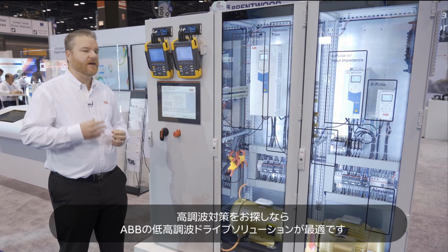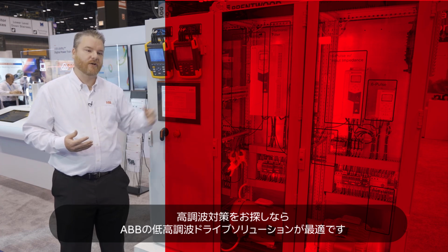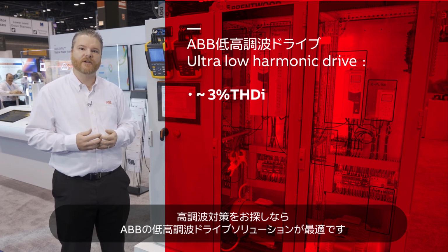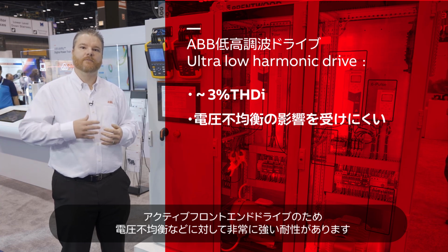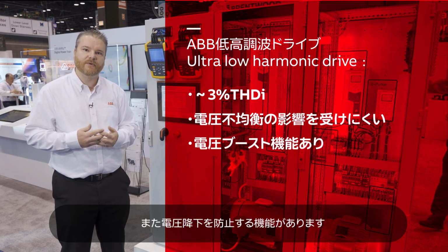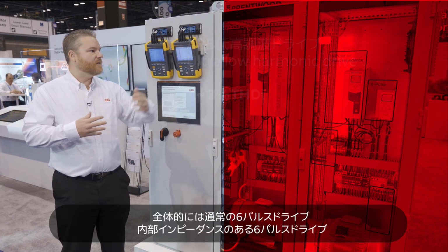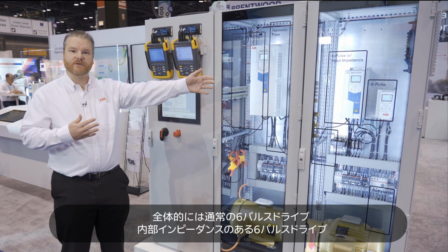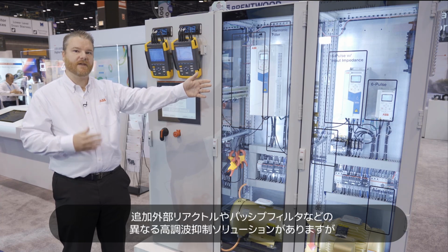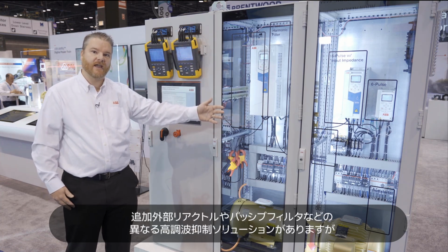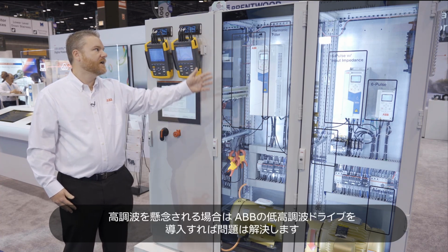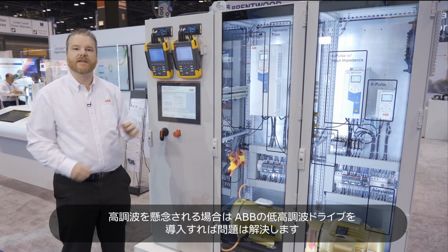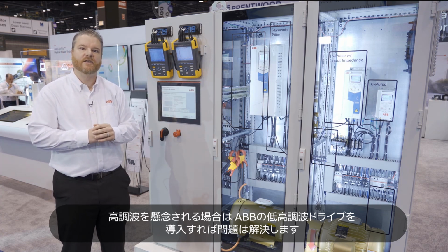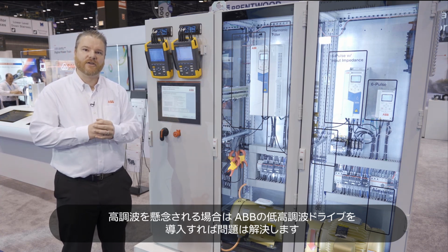So if you're looking for the ultimate in harmonic mitigation, the ultra-low harmonic drive is the solution for you. It's an active front-end drive. It's very immune to things like voltage imbalances. It's able to boost up the voltage if you have a low line situation. There's a lot of other advantages to it other than just harmonics. So overall, you've got your 6-pulse drives with no impedance. You've got your 6-pulse drives with internal impedance. You have different external solutions like extra reactors and passive filters. But the ultra-low harmonic drive is that drive. If you've got any harmonic concerns at all, install that drive and you're going to be good to go.